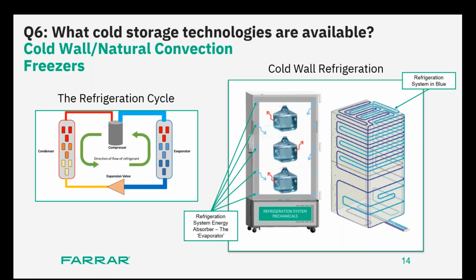However, cold wall freezers are fantastic instruments designed to make sure that if you are focusing on long-term storage with low frequency of door openings, it works really well, right? Once again, I'll go back to the biorepository example. When samples are coming in, you're storing them for an indefinite period, then you're not really opening that door. So once you reach equilibrium, samples are stored and safely nestled at minus 80 degrees C. You're not opening the door.